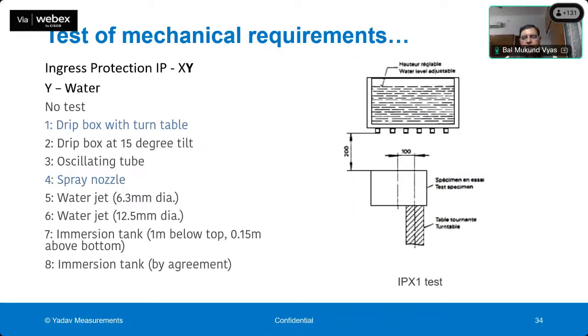Against water, the meter is subjected to artificial rain. There is a rain testing machine, and if the meter is of indoor type, meaning it is to be installed in a box, then it has to pass the first level of rain protection, or you can say water protection. The meter is subjected to artificial rain for 10 minutes. After the test, the meter is subjected to the insulation test, and is again opened to see if there is any water ingress. So the meter should be waterproof up to level 1.